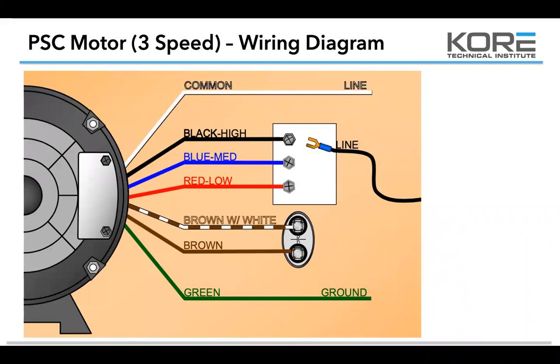So again, guys, depending on the speed you want to run on your indoor blower, you can energize these at different times too. You could hook up all 3 of those to different lines, depending on if it's a call for heat or a call for cooling. Cooling is usually going to run on high speed, and depending on the heat package, you might run it on medium or low speed, just to give time for that heat exchanger to warm up. So you might have a couple of these terminals hooked up. The only thing I would tell you is don't energize 2 of the speeds at the same time. So you're going to hook up your high and possibly your medium speed.